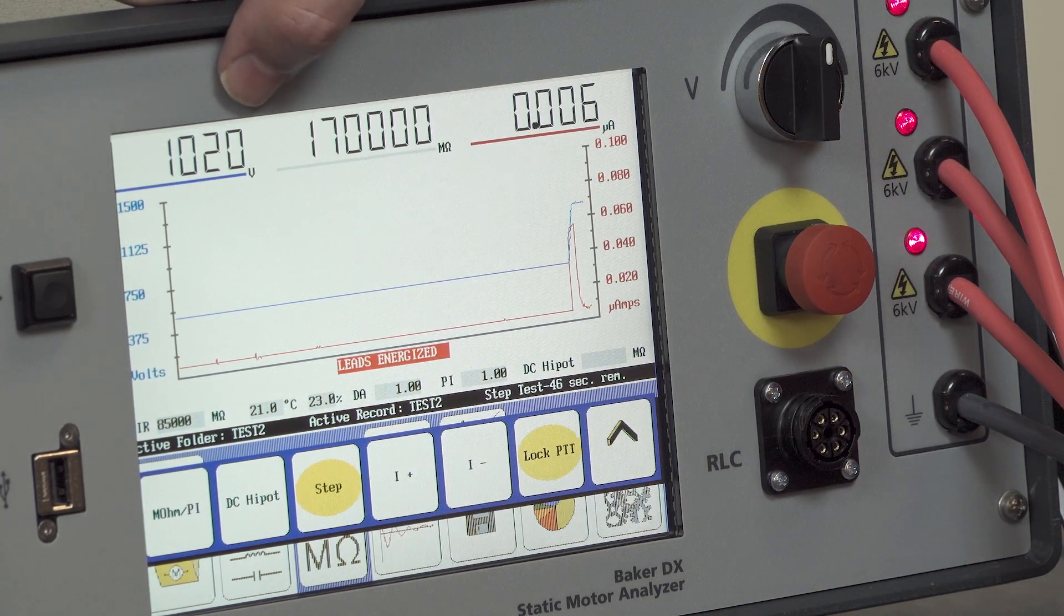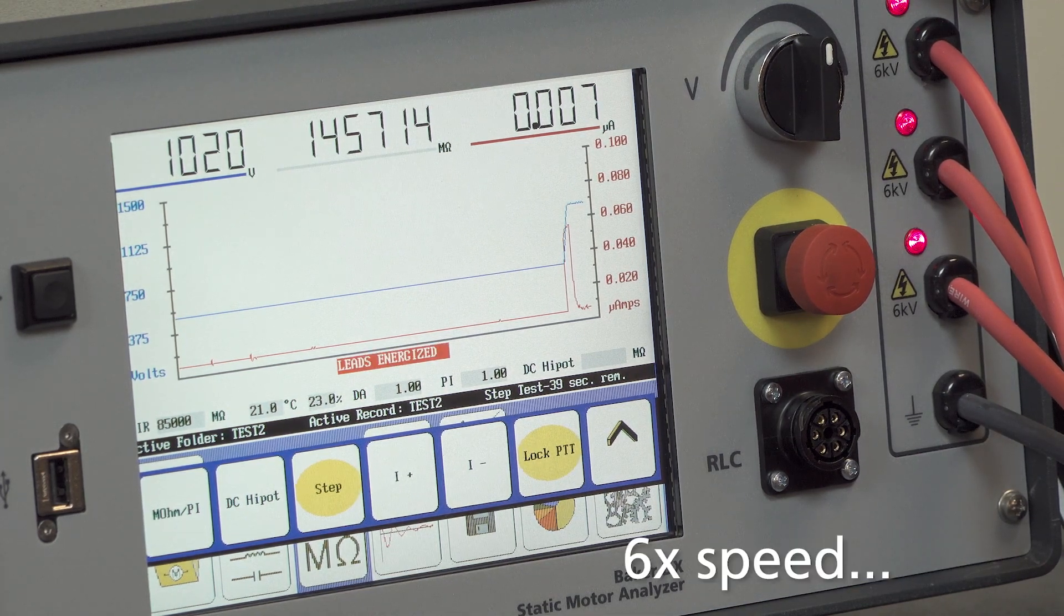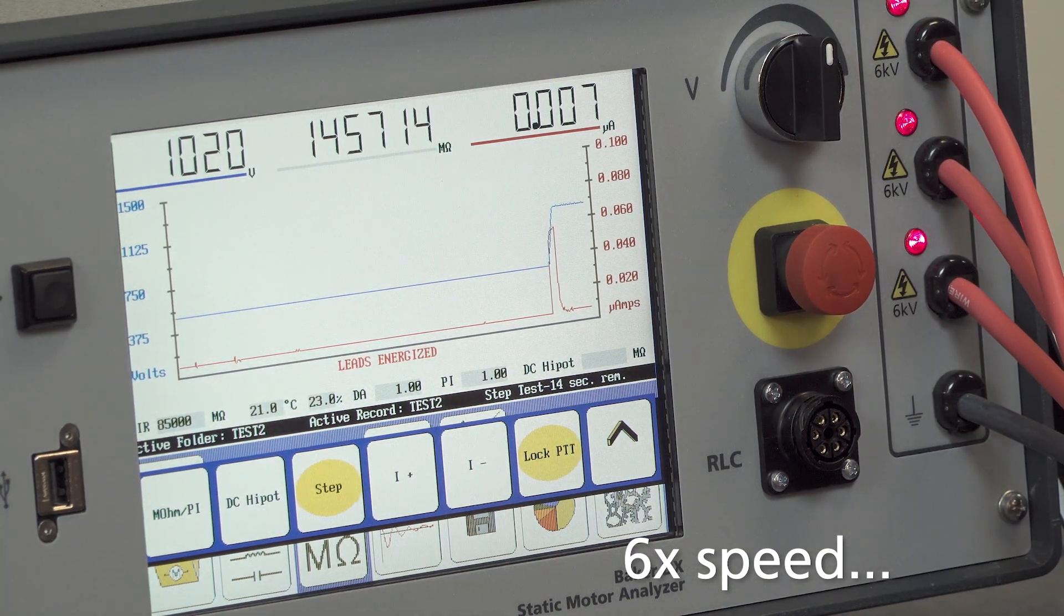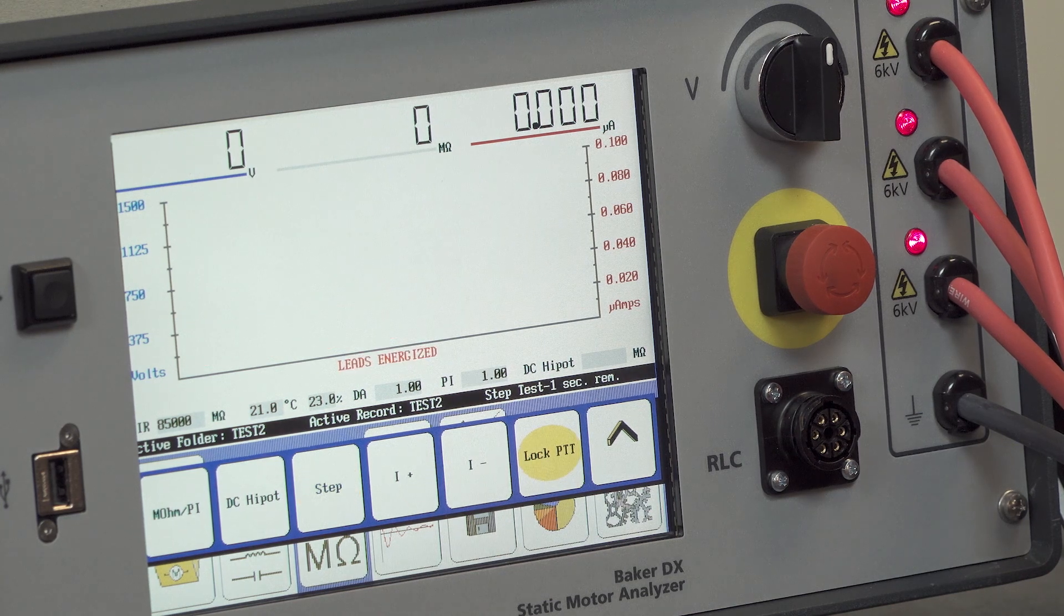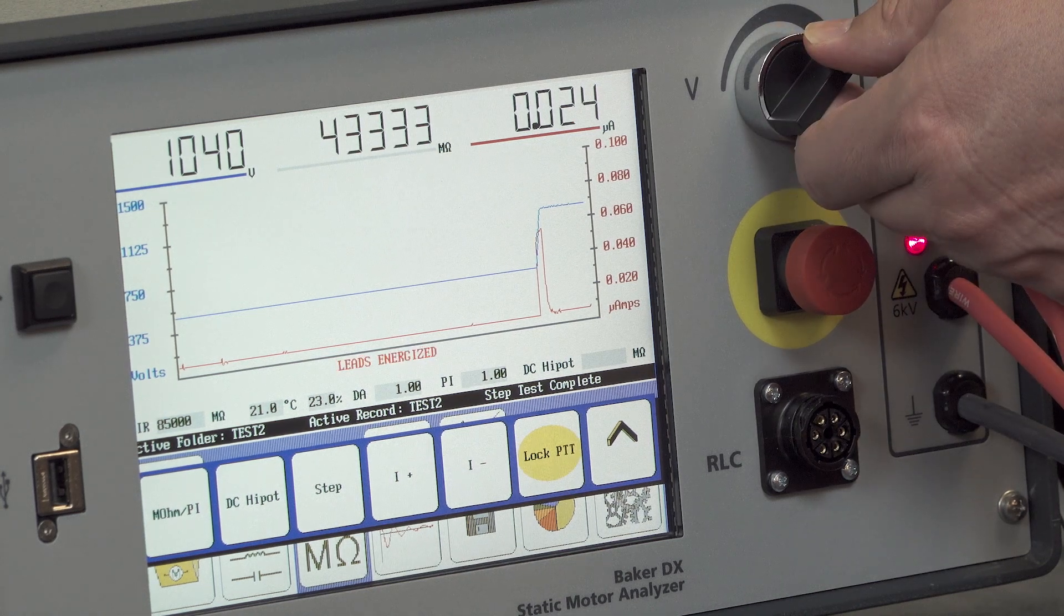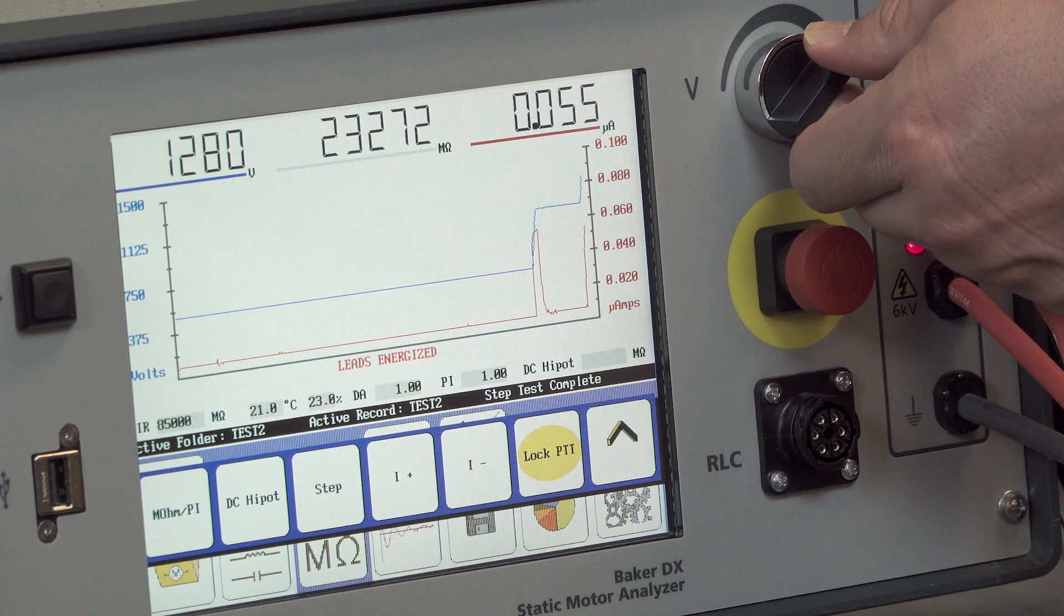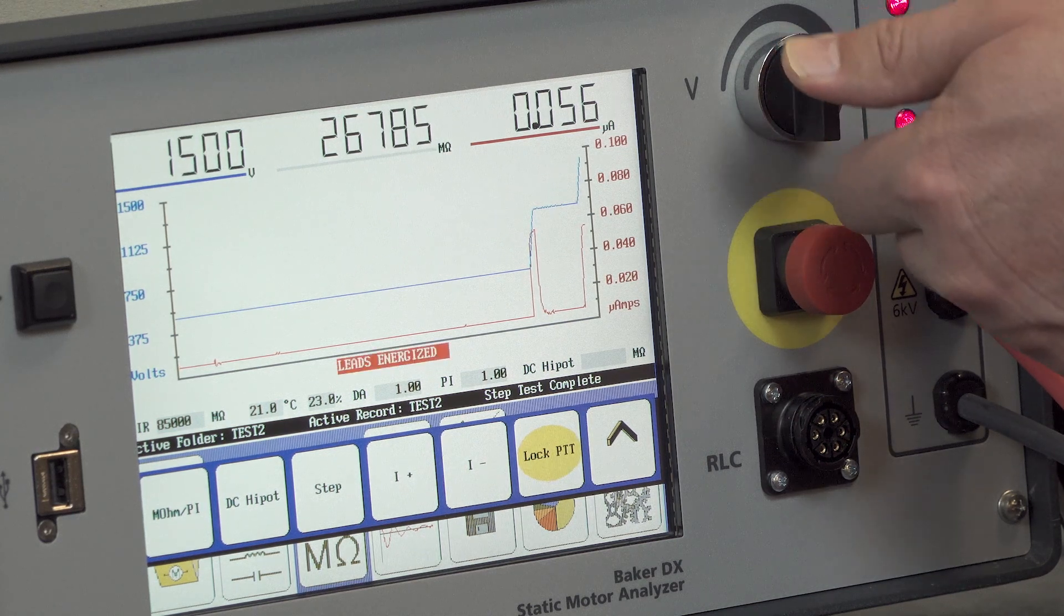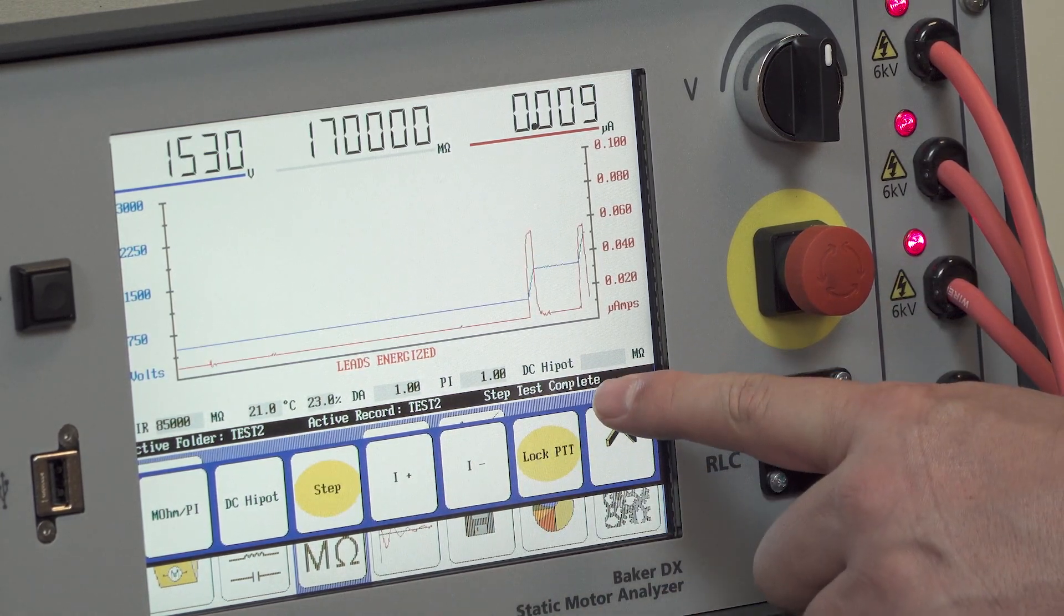And we'll perform the same steps again. Okay, now this is step test complete. I'm going to ramp to the next step which would be 1500 volts, watching the voltage here on the left. Okay, I'm going to achieve 1500 volts, I'll hit the step button again, restarting the step timer.